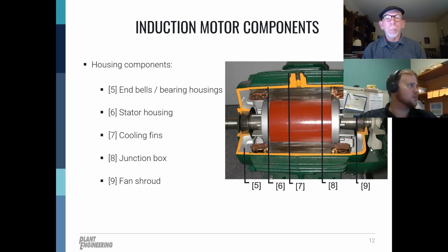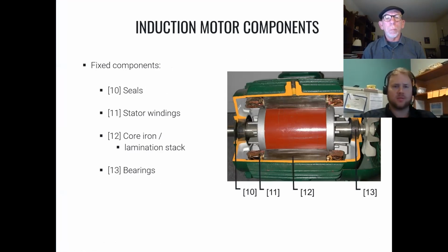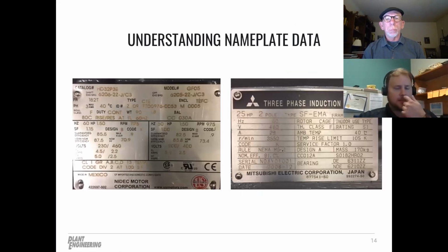We got one more slide on components. These are going to be some fixed components: the shaft seals, the stator windings, stator lams or stator laminations, and then you see the bearings. Of course, we reiterate in any of these trainings or presentations, the bearings are likely the most influential component on motor life. And we do have a slide later on where we talk about bearings and the leading cause of failure and whatnot. So now we've got a basic understanding of some of the components.